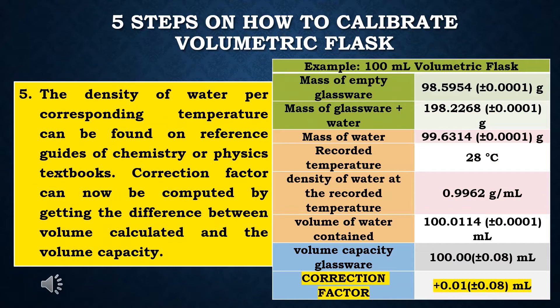Step 5: the density of water at a corresponding temperature can be found on reference guides in chemistry or physics textbooks. The correction factor can now be computed by getting the difference between the volume calculated and the volume capacity. In the example, the volume capacity of the glassware as found on the label is 100.00 ml. Correction factor equals 100.0114 ml minus 100.00 ml, giving a computed correction factor of +0.01 ±0.08 ml, rounded to the correct uncertainty in significant figures.